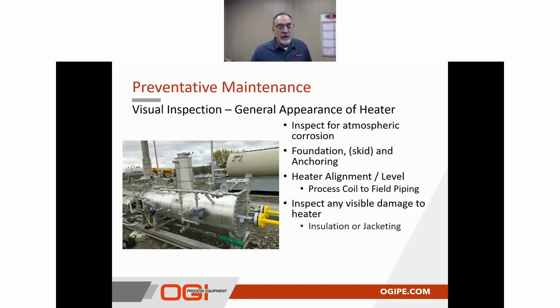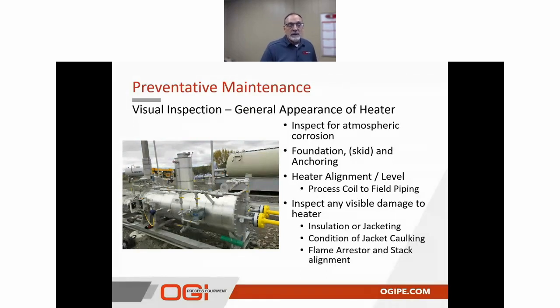First thing that's important is to do a physical inspection to understand the visual appearance of the heater, conducting a walk around to provide an overview of an as-found condition of the heater, inspecting for atmospheric corrosion on the paint, on the saddles, on end plates, on piping, inspecting the foundations and the skids and the anchoring of these heaters to those foundations, looking for cracking, whether the bolts are tight, and is the skid properly supported. Next is the heater alignment and the levelness of the heater.